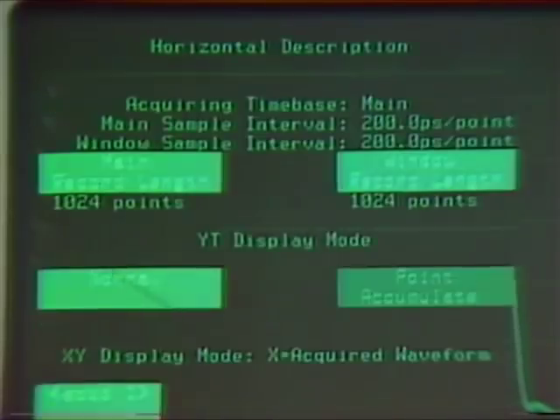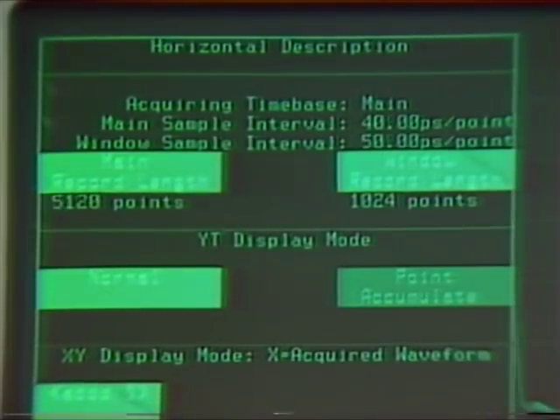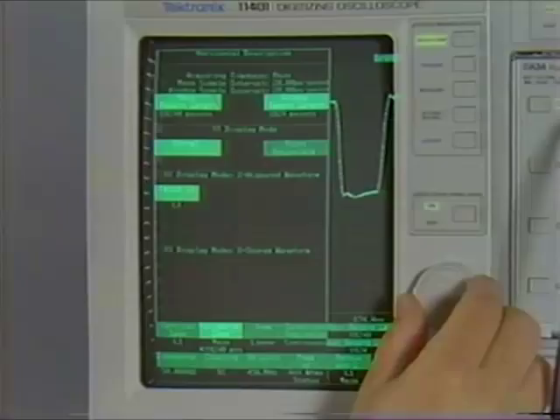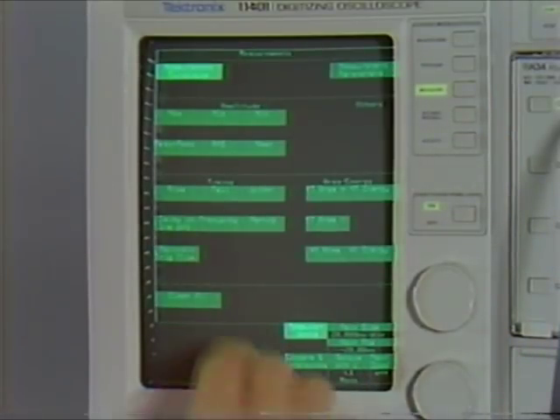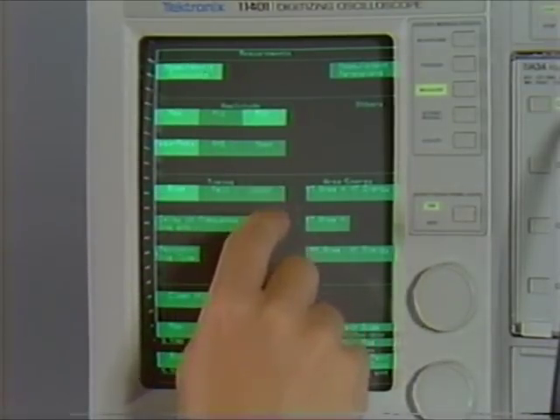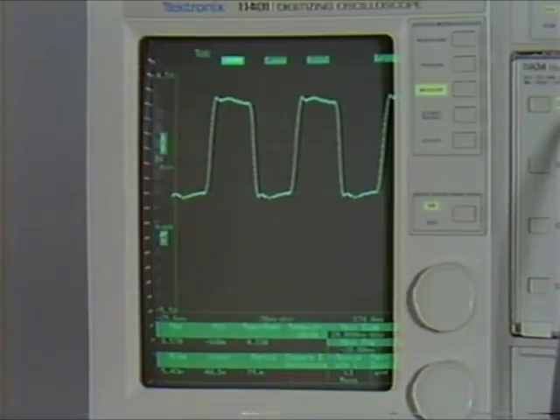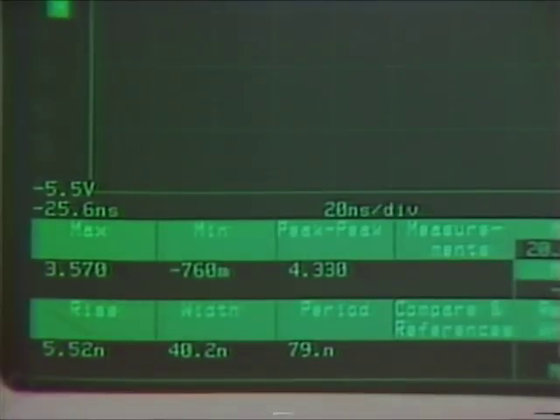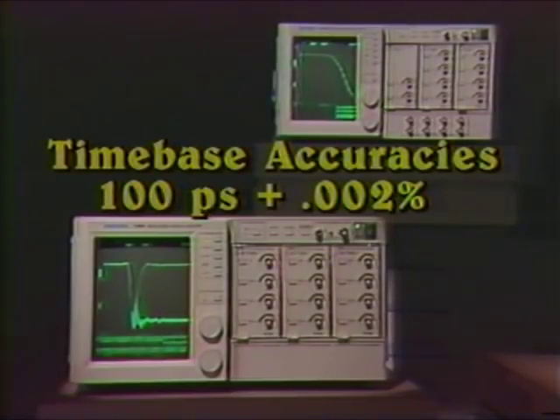Both mainframes can make single-shot, trigger-to-trigger timing measurements with 100 picosecond resolution. The 11401 and 11402 can acquire multiple records of up to 10,240 points each — no other scope can capture as much data at once on repetitive waveforms. With these long records, the mainframe can accurately measure width, period, amplitude, and rise time all on the same display. Generally, reacquisition isn't necessary to make sure enough points exist on an edge. The 11401 and 11402 are the most accurate high bandwidth scopes on the market, with timebase accuracies of 100 picoseconds plus 0.002% of the measured interval.